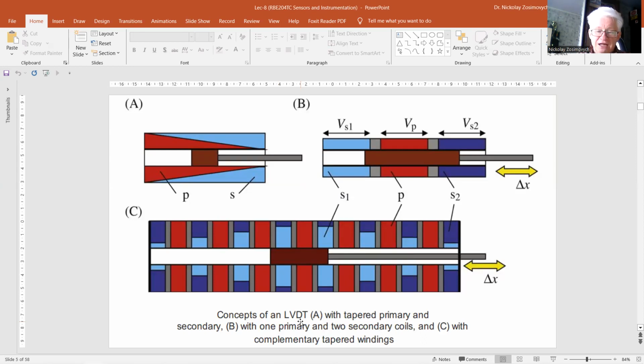Figure A, in the upper left corner of this slide, shows a linear variable differential transformer with one primary and one secondary coil. The coils have tapered windings in opposite directions. Without a paramagnetic core, the coils are only weakly coupled. The voltage on the primary coil gives only a small output voltage at the secondary coil. However, when a paramagnetic core with high permeability is inserted in the hollow cylinder, the coupling between the coils is much stronger at the position of the core.